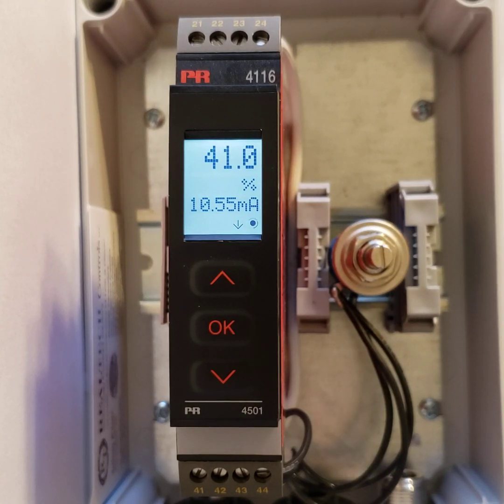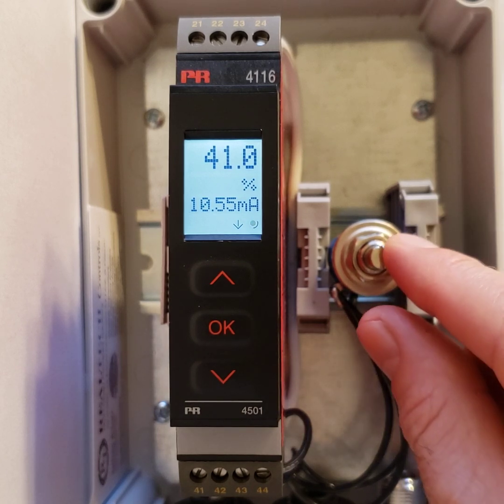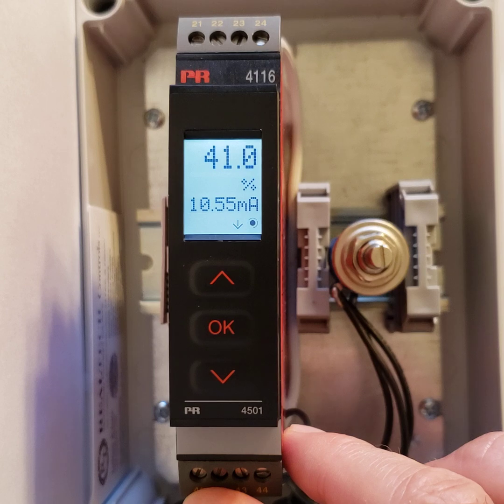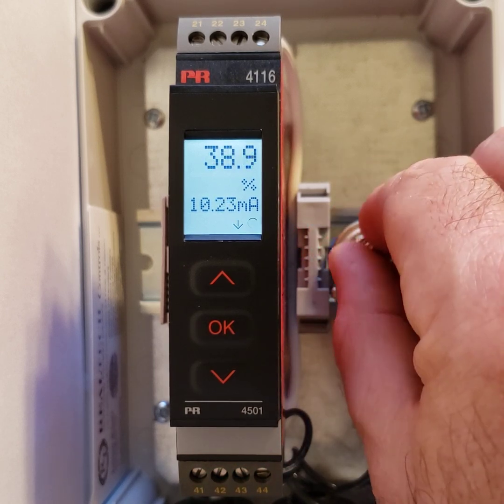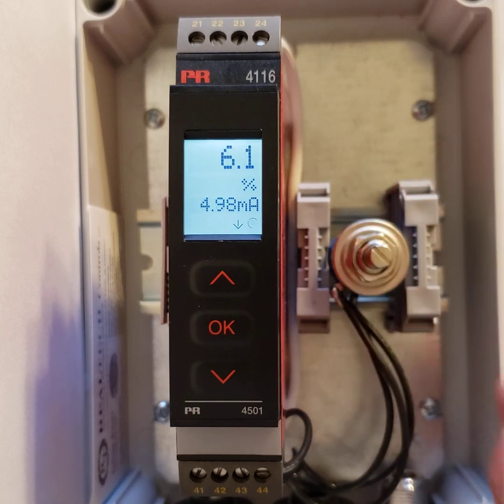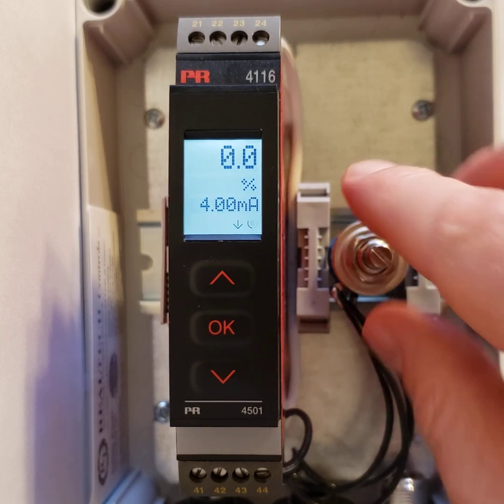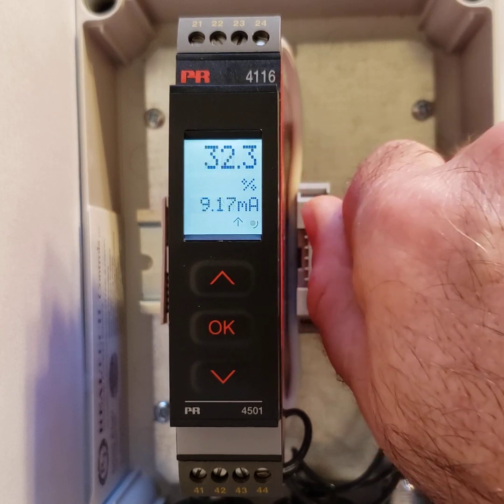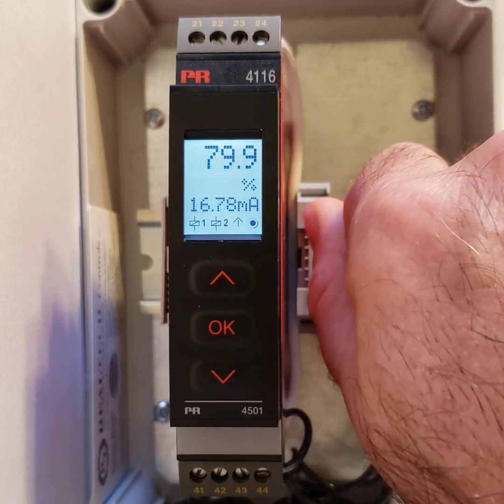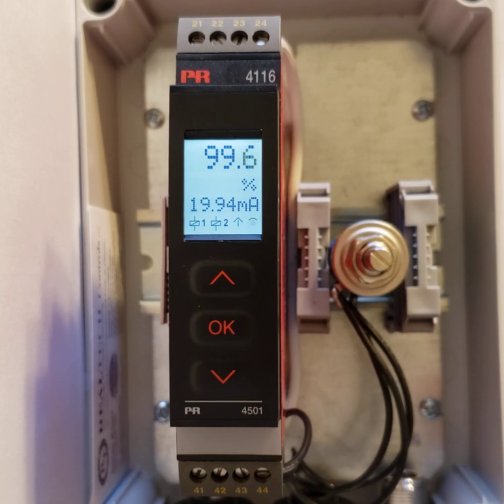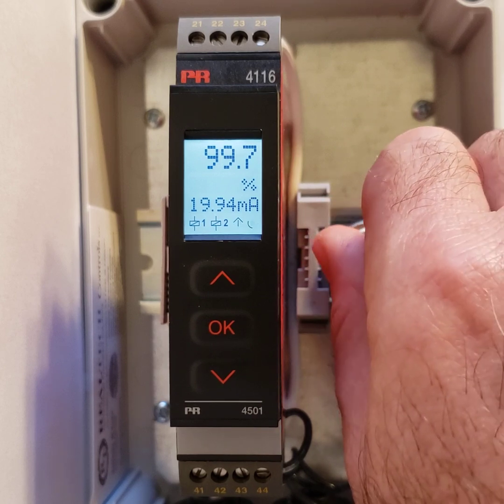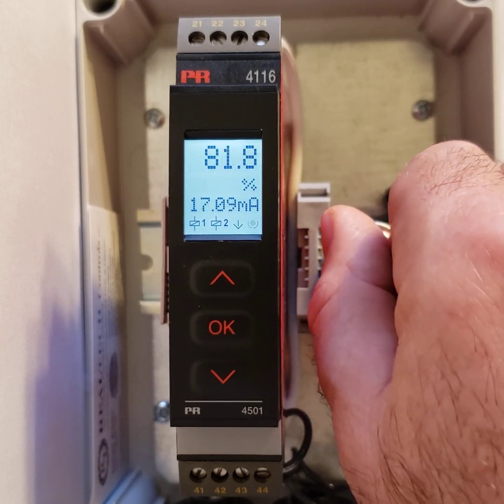I'm Julian with RealTech Controls, and I'm going to show you the programming of the PR Electronics 4116 transmitter in the advanced programming mode. I have a potentiometer attached to this device, the input, for 0 is equal to 4 milliamps. And if I scroll the pot all the way to the other side, 100%, or the pot only goes to 99.7, is equal to 20 milliamps, which we will calibrate out in the menu item a little bit later.